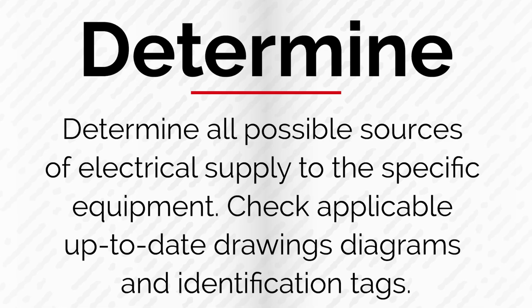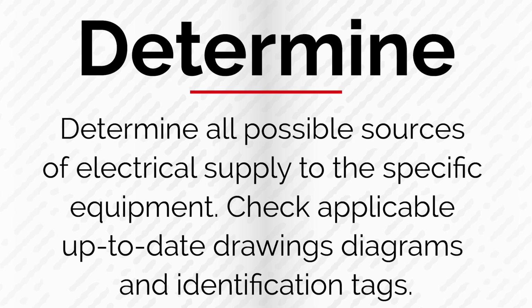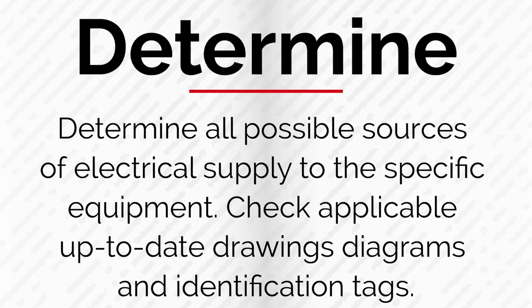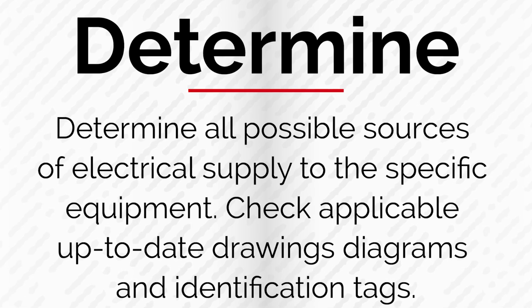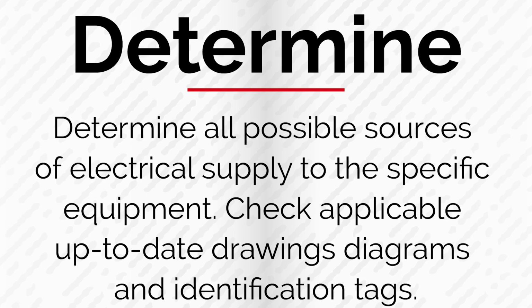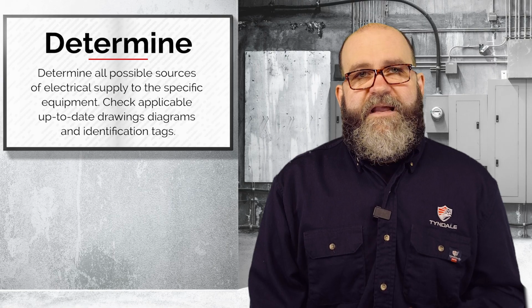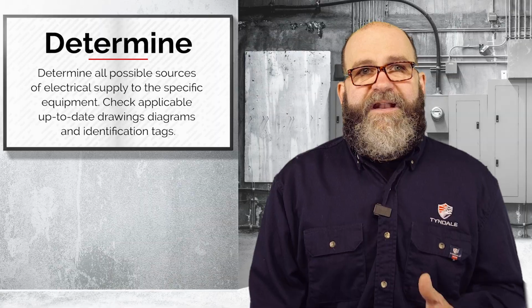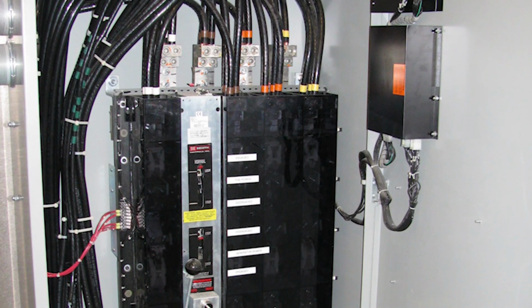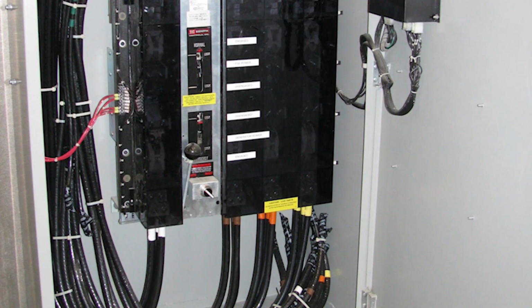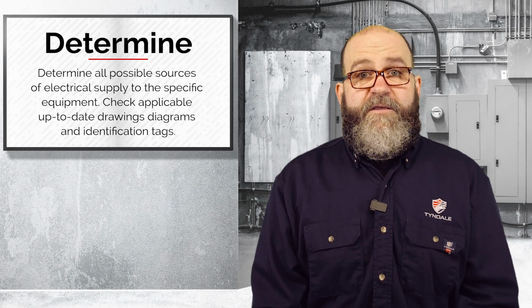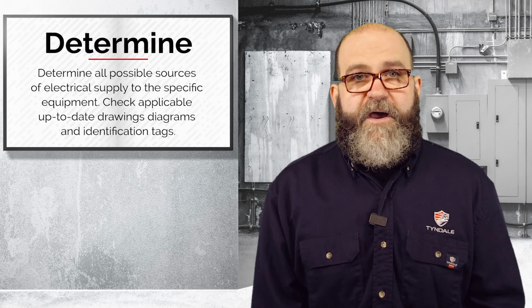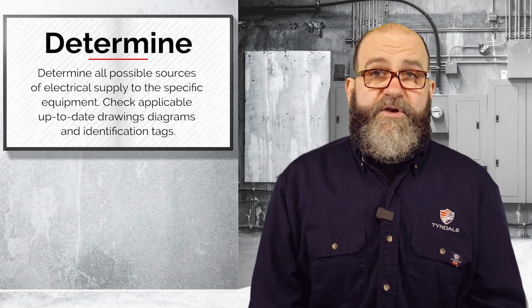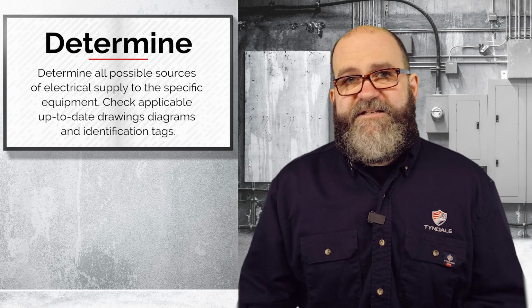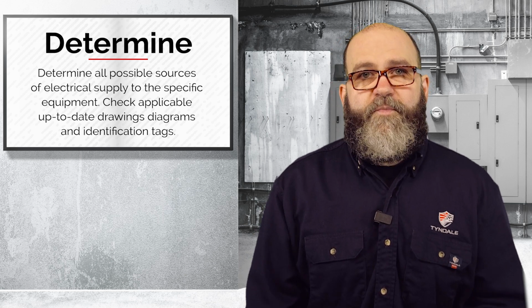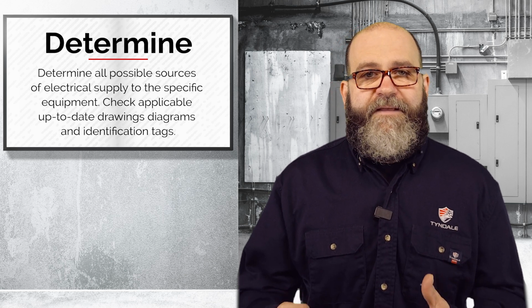Step 1 tells us to determine all possible sources of electrical supply to the specific equipment. Check applicable up-to-date drawings, diagrams, and identification tags. It's important to understand that it's not uncommon to have multiple sources of power in a single piece of equipment. A few examples might be transfer switches, right? You've got utility power, you've got generator power, etc. Or control cabinets, MCCs, etc. You can have multiple sources of energy and power in those enclosures.